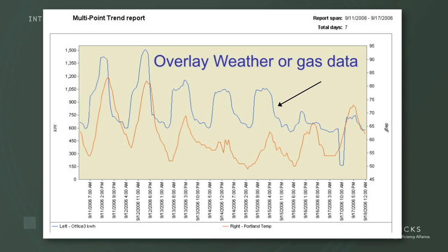And you can see how as the temperature goes up, you get to a certain point and the energy use goes higher on each day. As energy use goes down, this building is shut down in the evening. The temperature goes back up, but not as high. As you notice, this was only going up to about 65 degrees, where you're up at 80 degrees here, and so your peaks for those days aren't nearly as high.